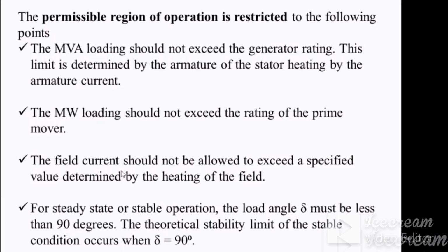Third one is that the field current should not be allowed to exceed, because if the field current exceeds the permissible limit, your reactive power is going to cross the limit, that is, it is not going to be within the boundaries and may start heating the alternator. So that is why your field current should not be exceeded, thereby controlling the heating of the field.